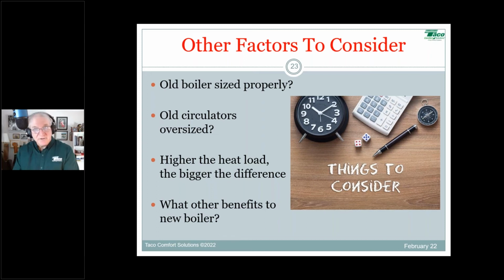The other side, of course, is maintenance is now a way of life. It's not like that old cast iron boiler that you really didn't have to do much to. Annual maintenance on a modulating condensing boiler is a must. You've got to treat the water - that's a must as well. So there are other factors that come into this besides just the numbers we're sharing with you here. This is part of the equation, but there's a lot more to it. So those are all different things to consider.